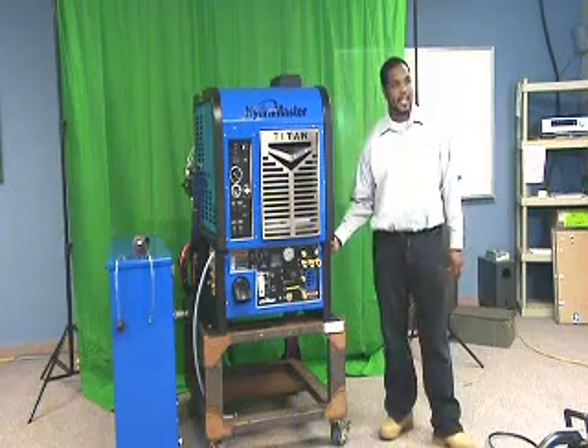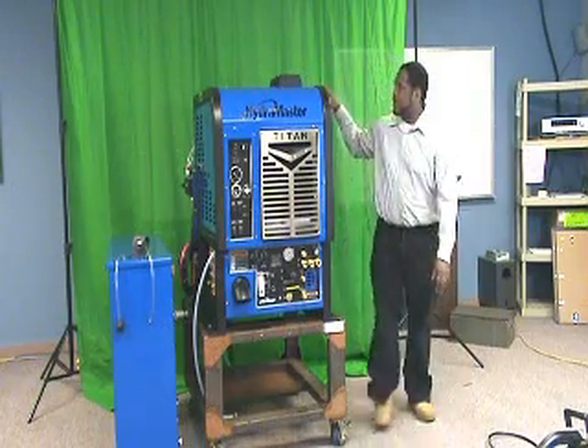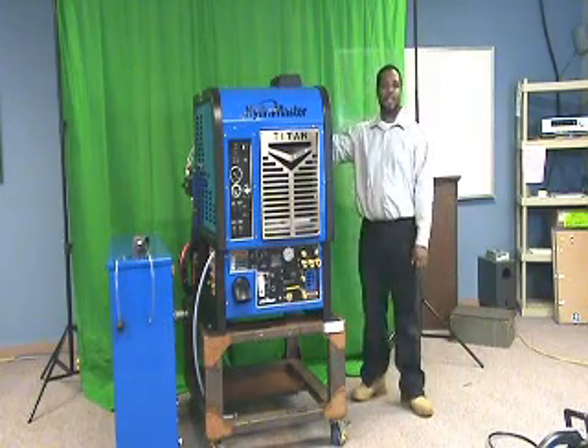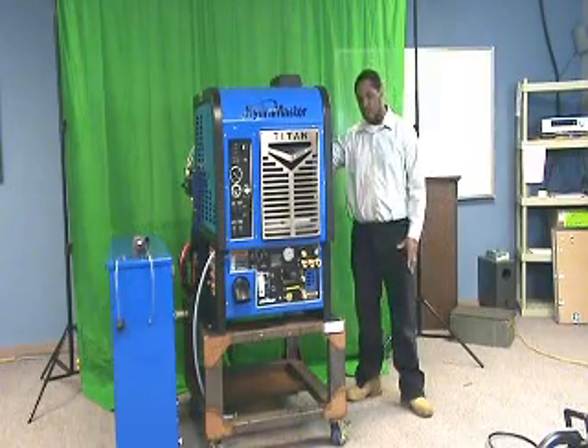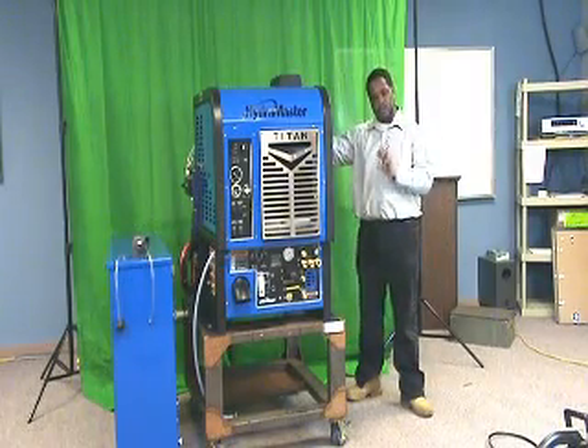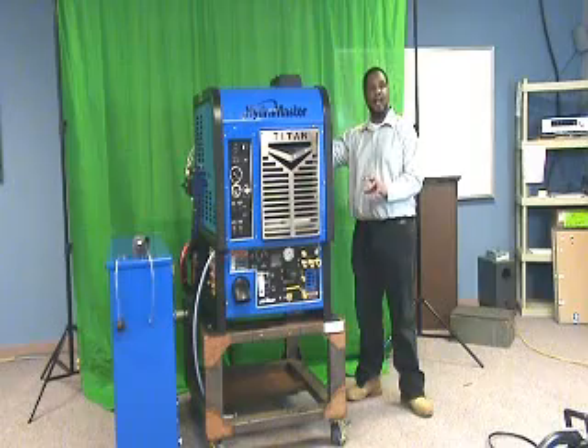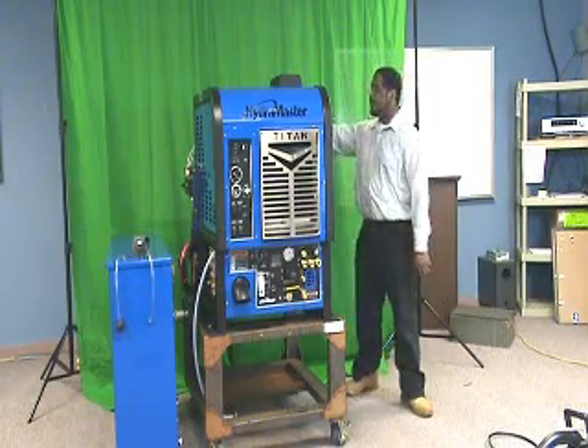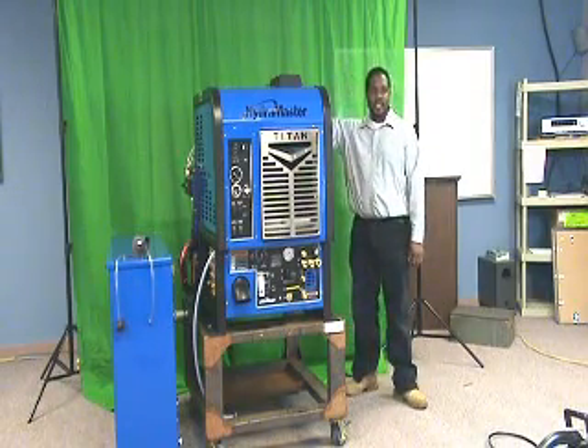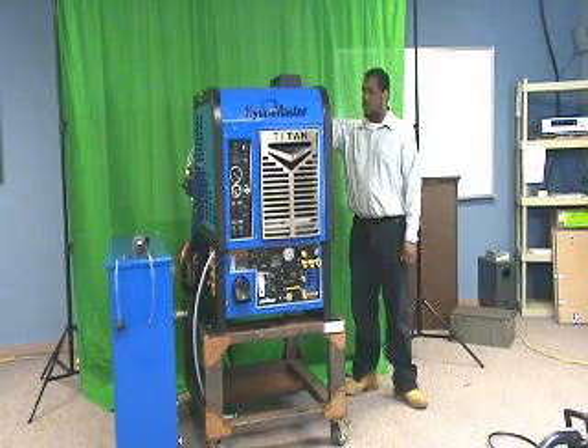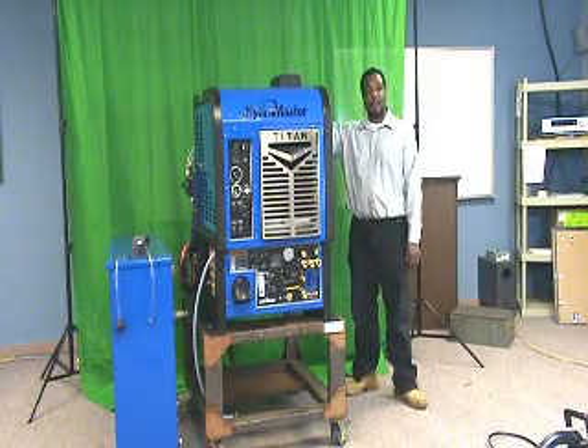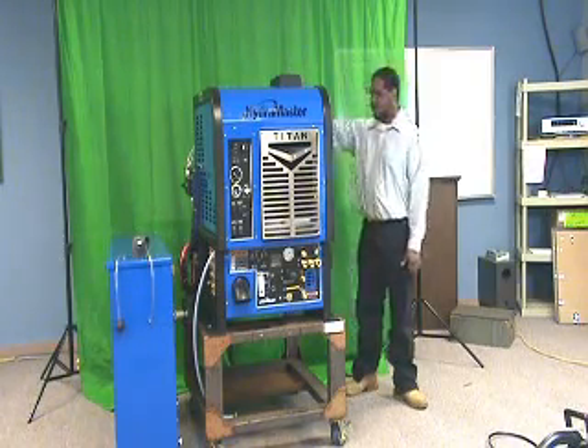So to descale the machine, we recommend using the TM descaler that we provide. We found it to work very well with our heat exchangers, with the fittings, so you don't have any sticking valves or any low flow through the fittings. Put the recommended amount of descaler inside the water box. Put the recommended amount of water with the descaler in the water box.